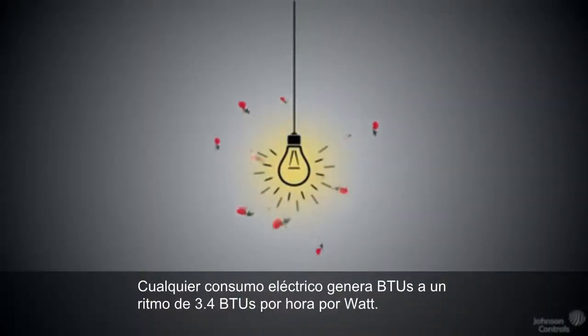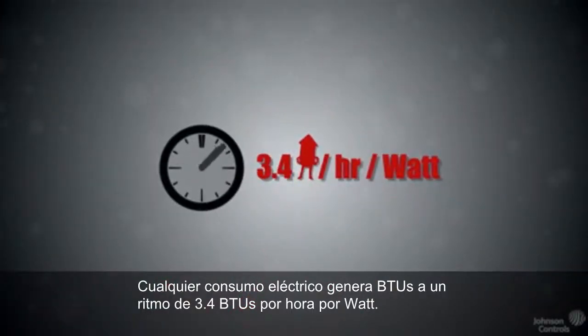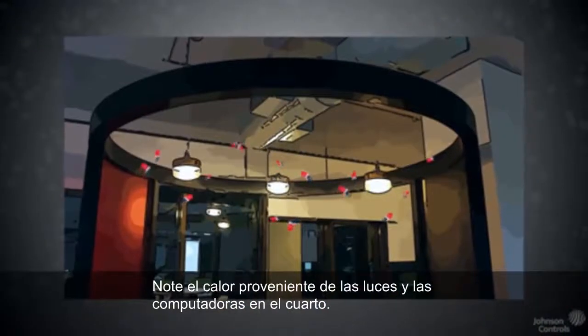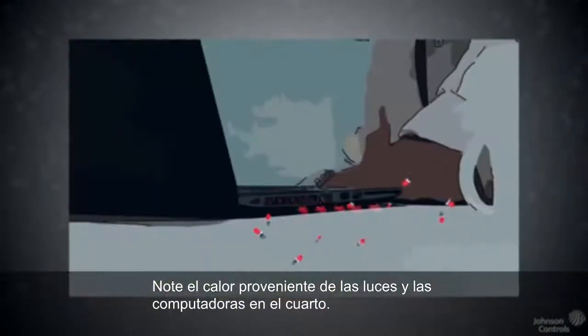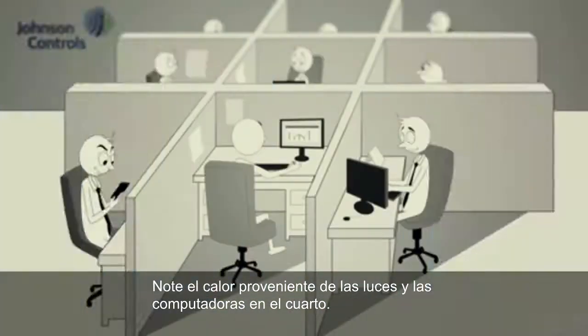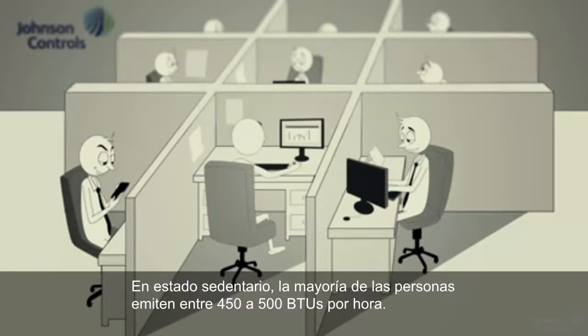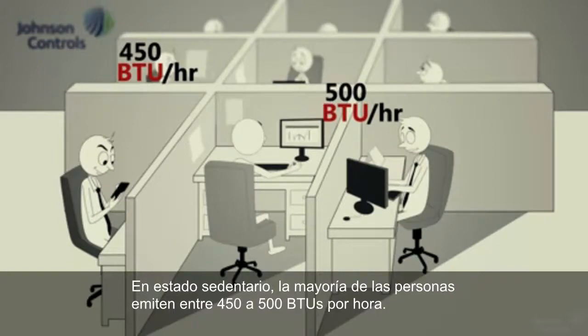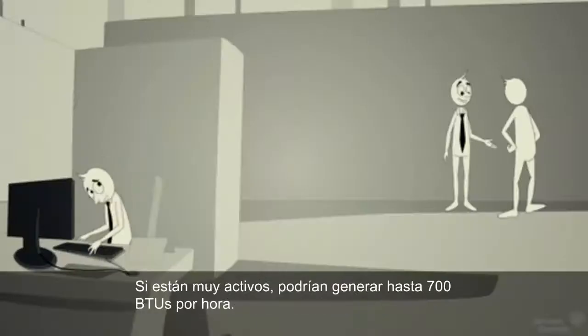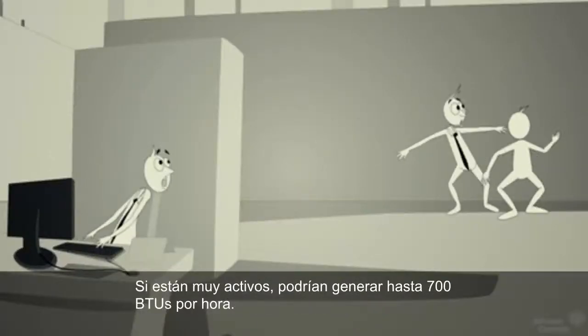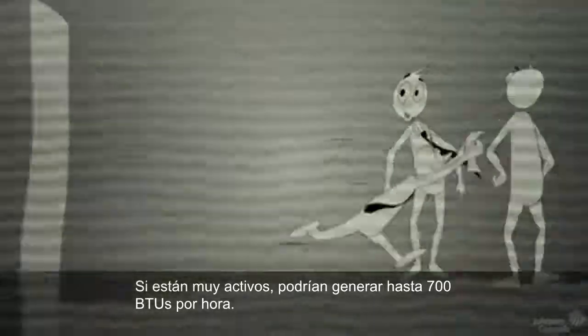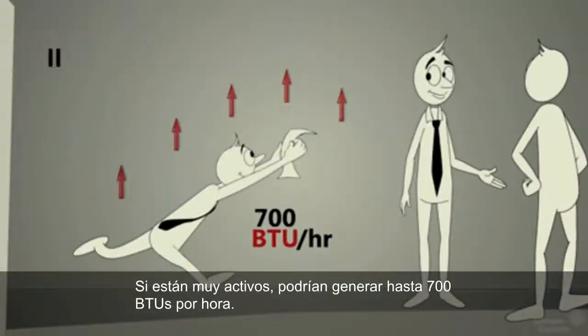Any electrical consumption generates BTUs at a rate of 3.4 BTUs per hour per watt. Notice the heat coming off the lighting fixtures and the computers in the room. In a sedentary configuration, most people will generate 450 to 500 BTUs per hour. If they are very active, they could be generating as much as 700 BTUs per hour.